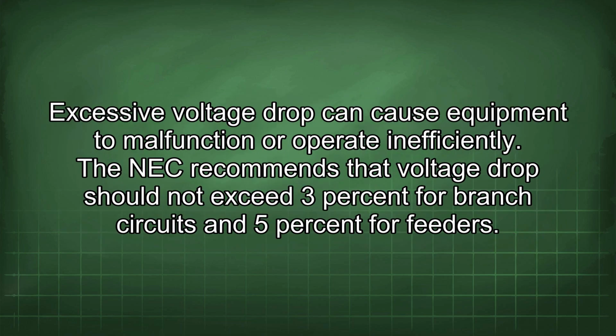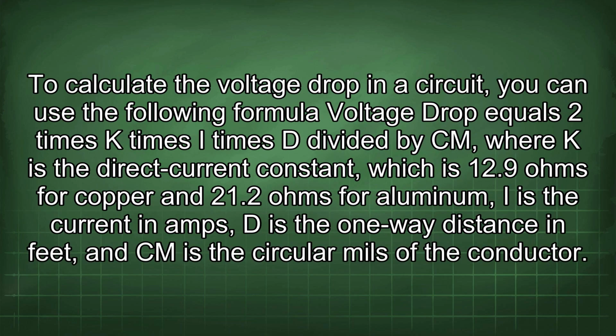Excessive voltage drop can cause equipment to malfunction or operate inefficiently. The NEC recommends that voltage drop should not exceed 3% for branch circuits and 5% for feeders. To calculate the voltage drop in a circuit, you can use the following formula: voltage drop equals 2 times K times I times D divided by Cm, where K is the direct current constant, which is 12.9 ohms for copper and 21.2 ohms for aluminum.